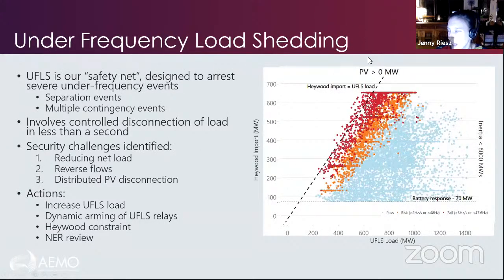The final element that we've been looking at is around our under-frequency load shedding schemes. So these are a safety net that is used to arrest very severe under-frequency events. So events where we have multiple units tripping at the same time, or the loss of a major interconnector separating a part of the grid. For these types of very severe events, we rely on these relays in the network that will detect that severe under-frequency event and trip off chunks of load, which will help to rebalance the generation that's been lost and hopefully arrest the frequency decline before it goes into a cascading failure.